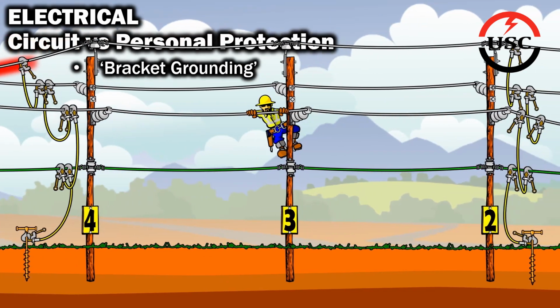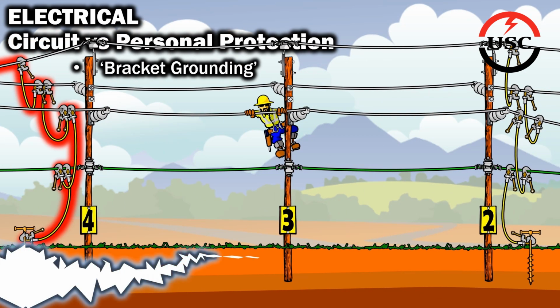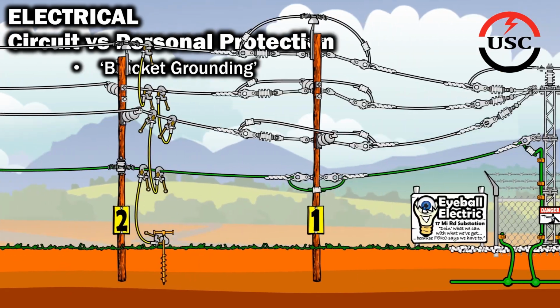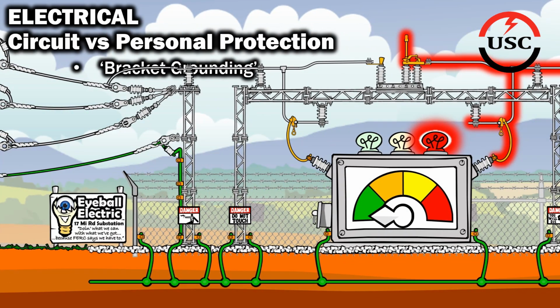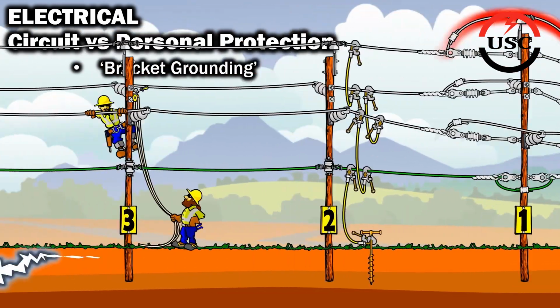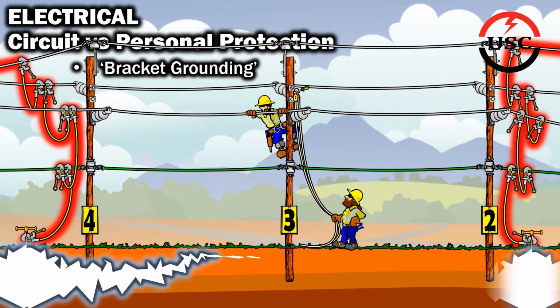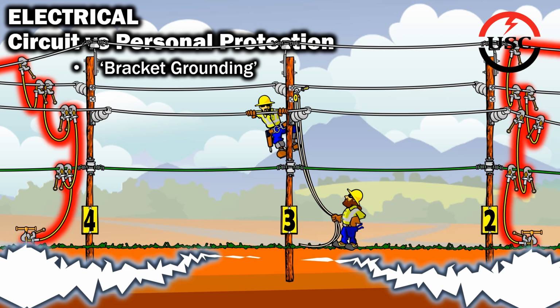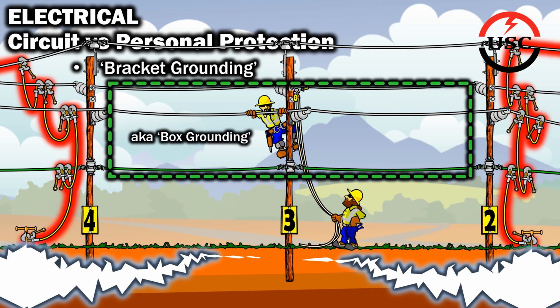example, then the load side of grounds would intercept and channel that fault current away from the worker. And if the line became energized on the source side, as in someone accidentally closing a switch, then the source side of grounds would intercept and channel that fault current away from the worker. In essence, it was commonly believed that the worker was safely boxed in, which is why bracket grounding is sometimes referred to as box grounding.